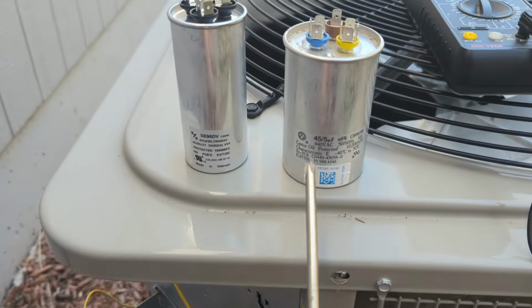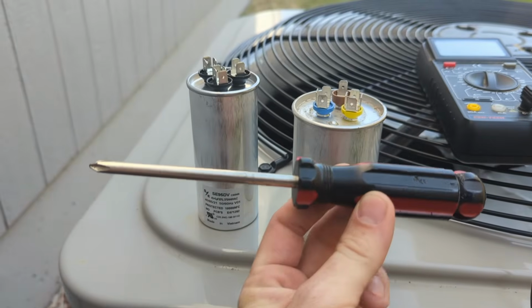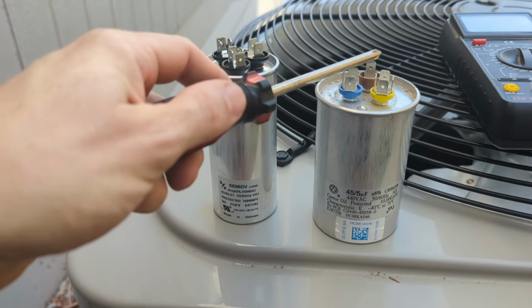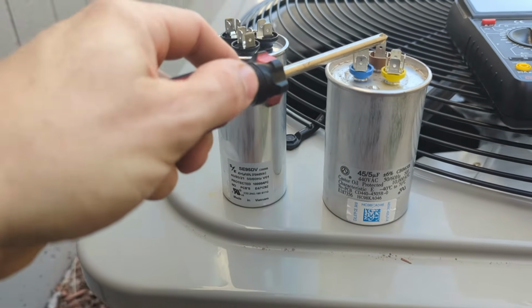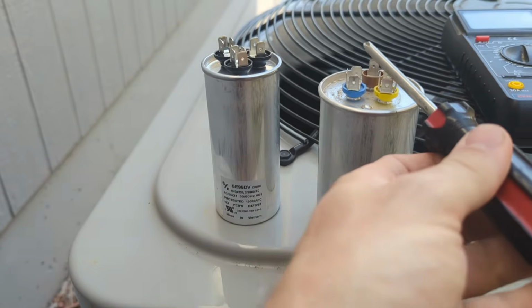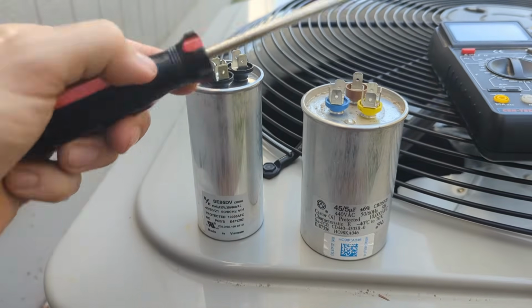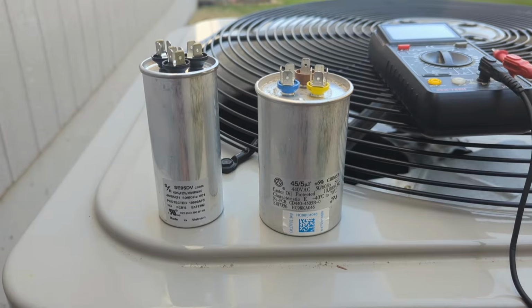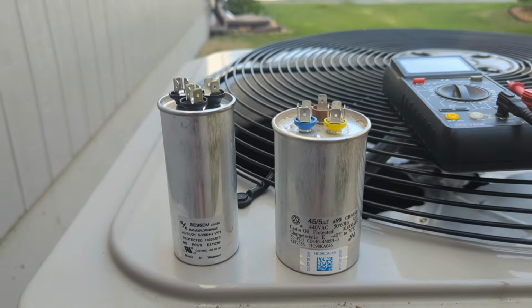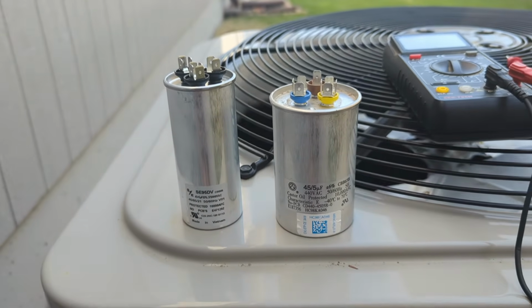So once I've pulled this one out, first thing I want to do is take an insulated handled screwdriver and touch it across the terminals here. Make sure I'm making good contact across terminals. That'll discharge any stored electricity in the capacitor. It can give you a pretty good zap, and you want to avoid that. Now that it's discharged, we're going to get our multimeter out and test it.